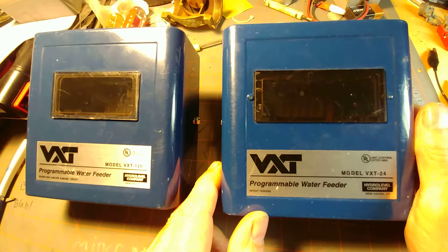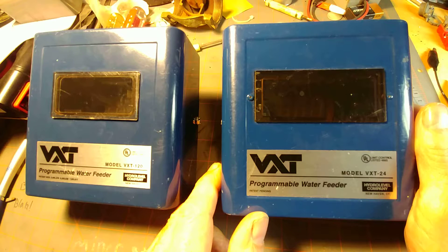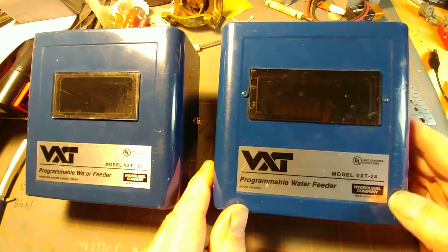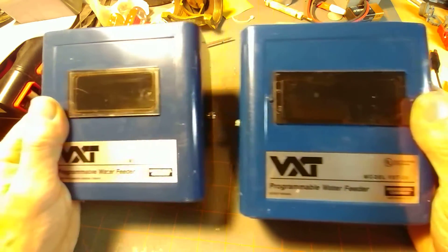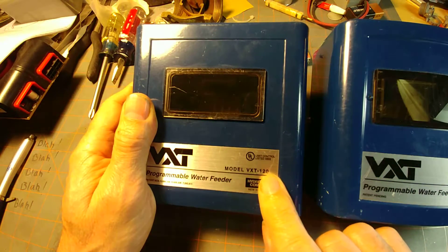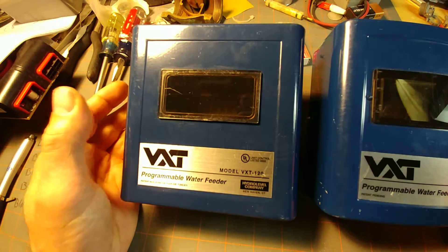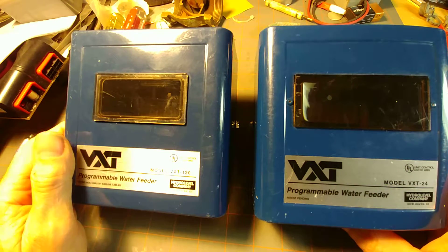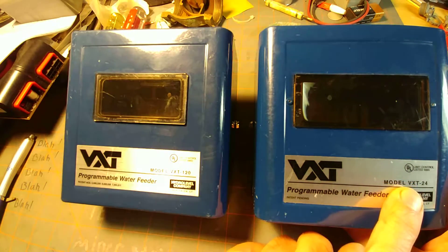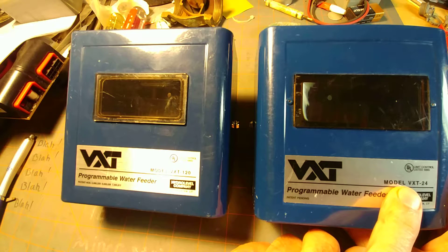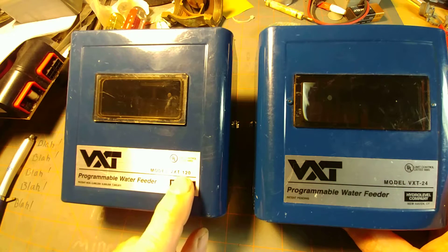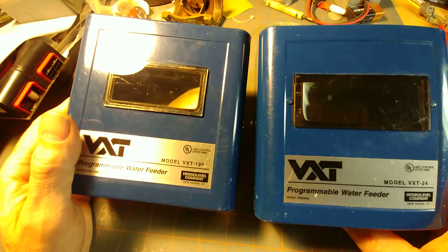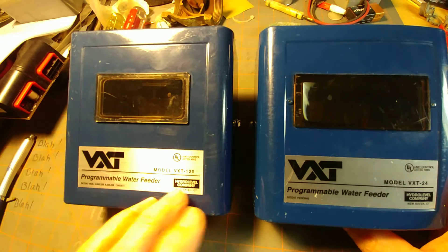Today we're discussing tips and characteristics of the VXT programmable water feeder made by the Hydro Level company of New Haven, Connecticut. It comes in two basic varieties: 24-volt and 120-volt units. You want to make sure you have the proper unit for the appropriate voltage of your boiler. In general, 24-volt units are found with atmospheric natural gas or propane steam boilers, and 120-volt units are found with power gas or old-fashioned oil-fired boilers.